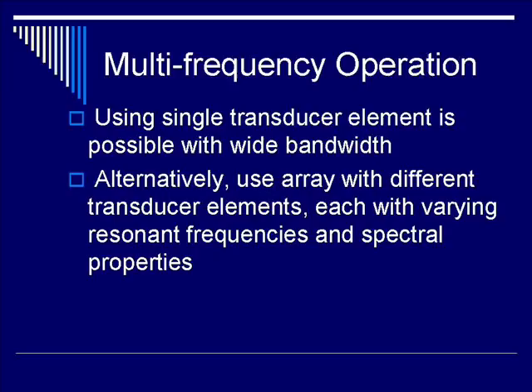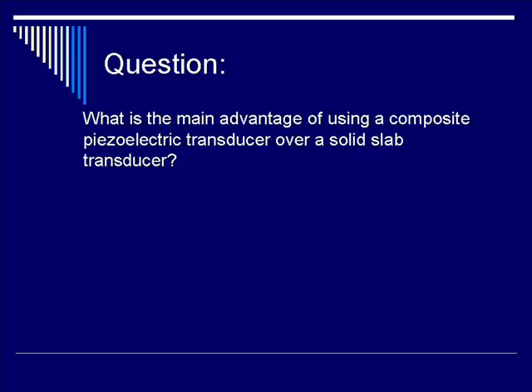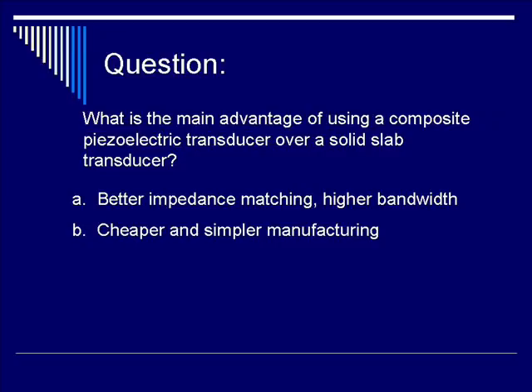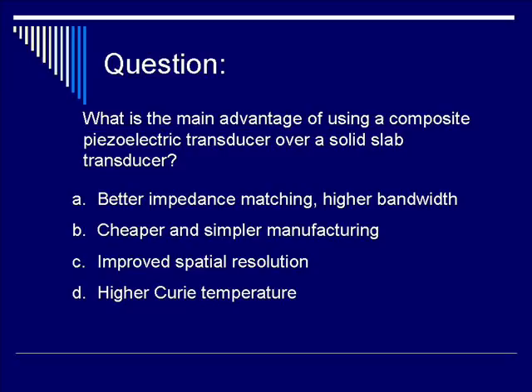Question: What is the main advantage of using a composite piezoelectric transducer over a solid slab transducer? Is it A, better impedance matching and higher bandwidth? B, cheaper and simpler manufacturing? C, improved spatial resolution? Or D, higher Curie temperature? The correct answer is A — better impedance matching and higher bandwidth. This is due to the composite material having a much lower Z that matches better with soft tissue impedance.